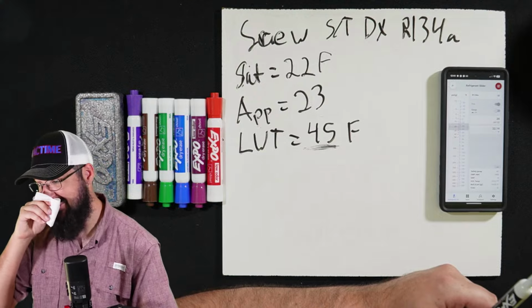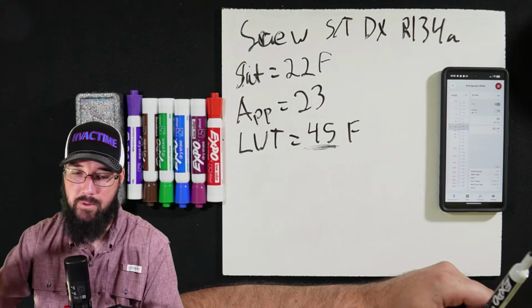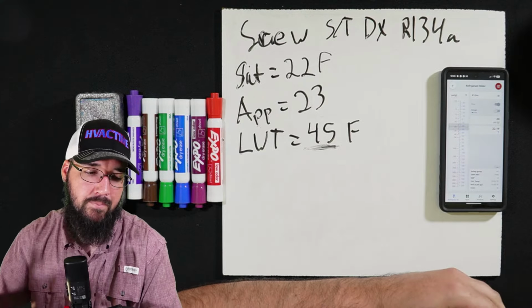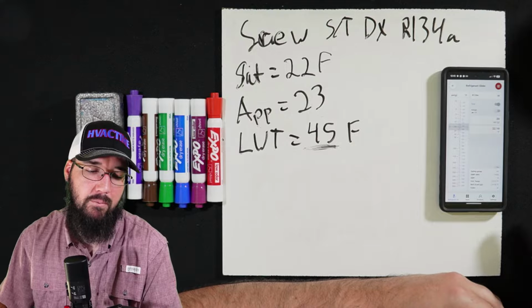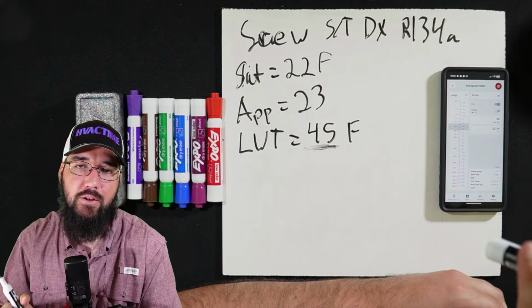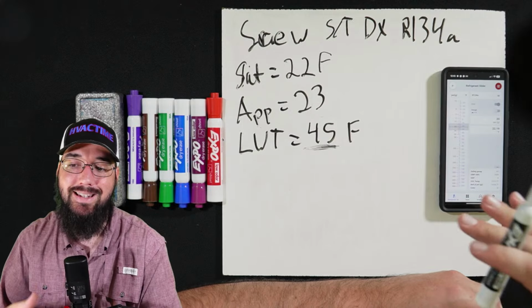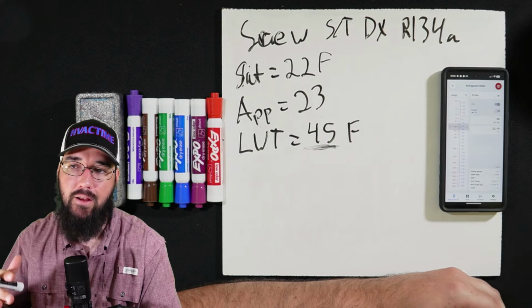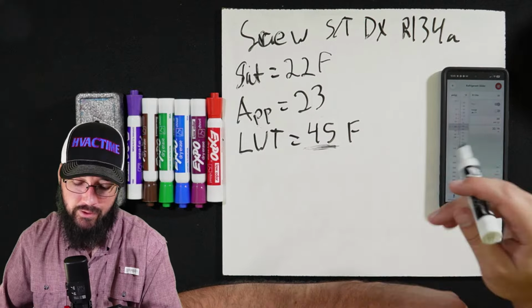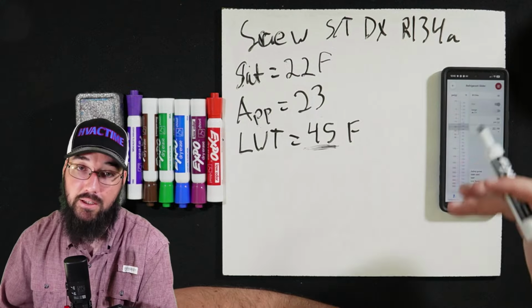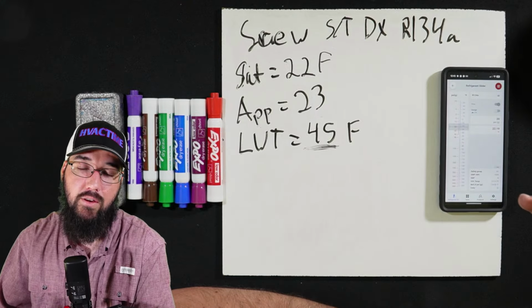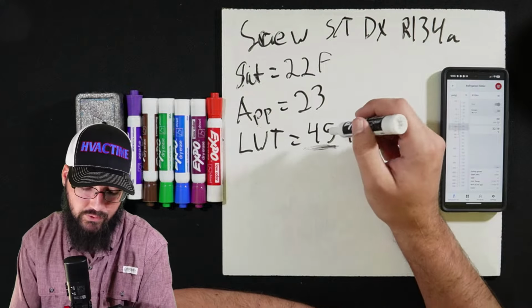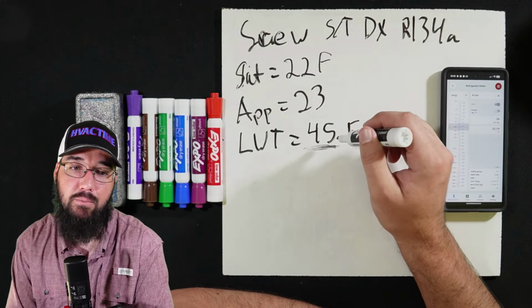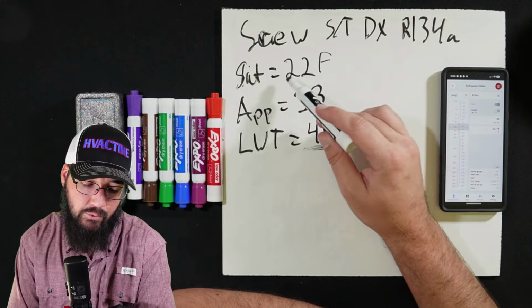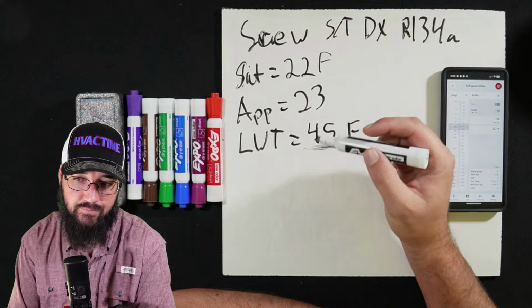Okay, so we may trip at, say, it may do a shutdown. When I say trip, I mean shutdown specifically. We may shut down the chiller at 2 to 3 degrees below set point. That's not what we're seeing here, but that's what you would expect to see with a low load. What we're seeing here is we are maintaining our set point temperature relatively, but we've got a really low saturation.